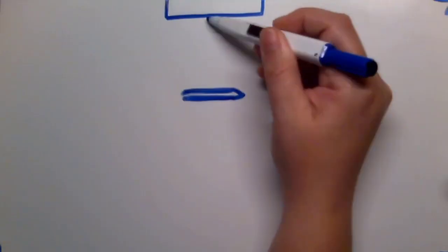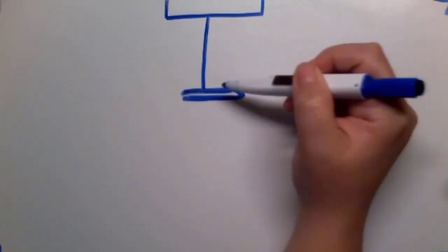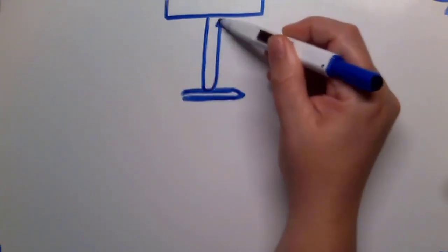So I just want to draw this out one more time for you. Reverberation is one of those artifacts that we're going to see quite often. So here's our transducer. Here is our really strong reflector. There's usually a couple of them really close to each other, so let's pretend like we're using a needle in the body. So that first sound is going to come back, strike the needle, and it's going to send an echo back. And so our picture puts a bright line there.